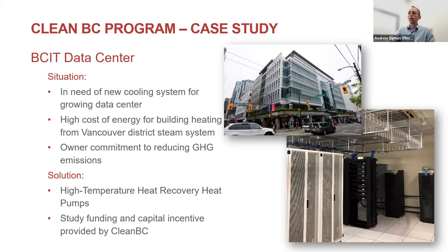This was a great project for a few reasons - we hit on a few sweet spots. There was a data center in the existing building venting most of its waste heat out through the roof, not being recovered or reused. There was a fairly high cost of energy because of the steam connection. And the owner was looking to do mechanical upgrades regardless - the data center was growing and needed additional cooling capacity. That's really the kind of project that's ideal for these custom studies: when you need to do something anyway, why not take advantage of one of these programs, do an energy study at the same time, and find the most efficient way to go about what you need.